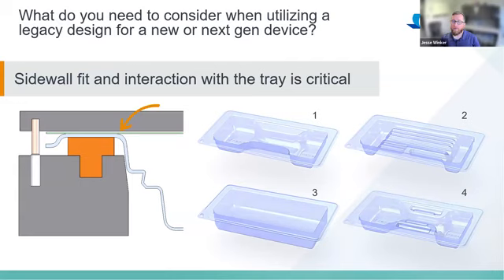This does come up quite often, and there's good value in being able to utilize some of your legacy system, whether that's a seal nest and seal head combination with just a new tray. We get that request a lot, and the things we really need to consider are: if it's a legacy design, how was that nest built the first time, so that the new tray can interact and fit within the nest appropriately. Looking through these four different tray versions, they're the same seal flange, but the interior geometry can play a big factor in whether it's actually going to fit within that nest, depending on how the nest was built the first time. If the nest was built around design number 3 here, it's got a big open area and can accept pretty much any of the geometry you'd want to put within that seal flange footprint.